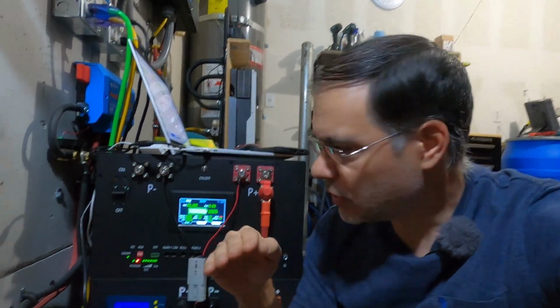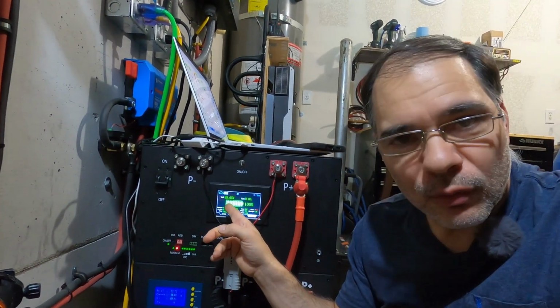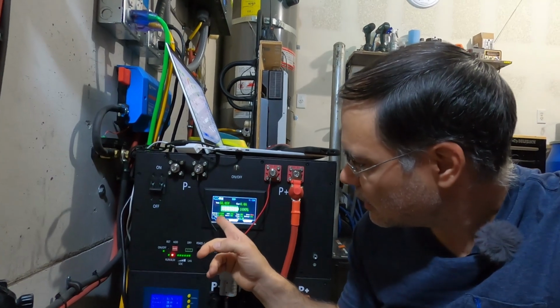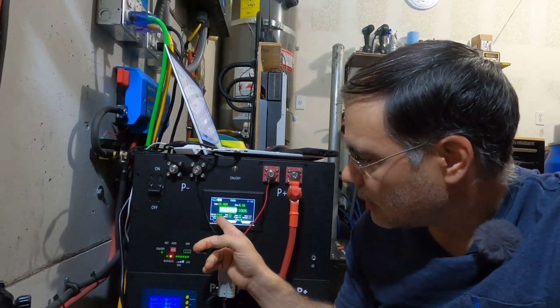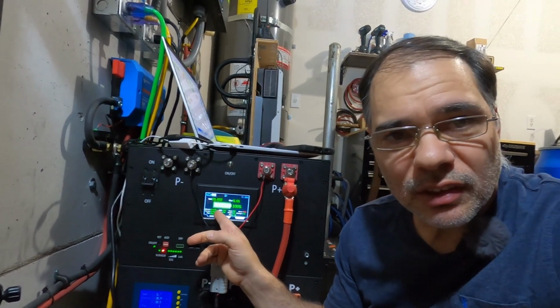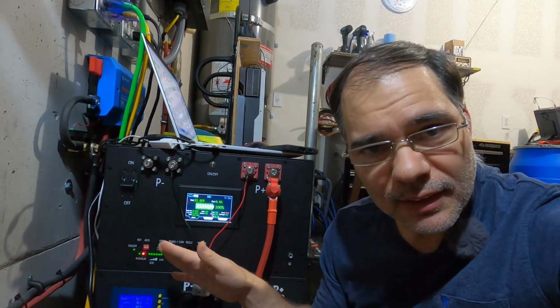What you're finally going to notice is all your voltages will settle above 3.40 volts. Once you're resting at 55 volts or higher with a relatively low deviation of like 20 millivolts or less, then you're in a good position to make a final push.